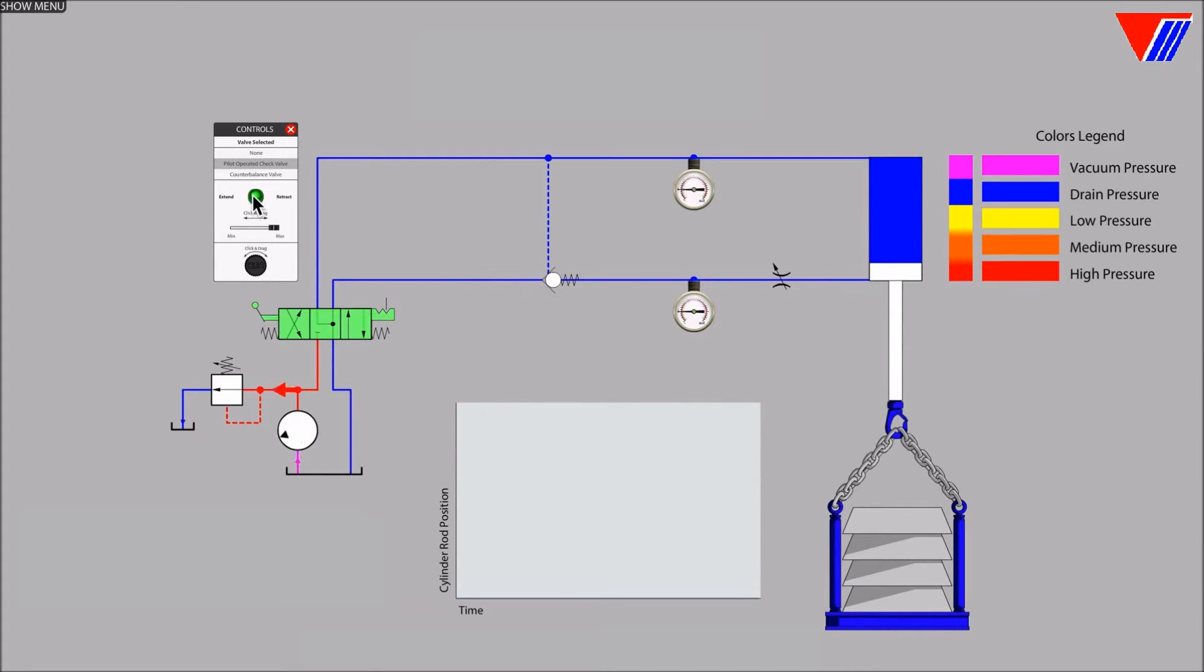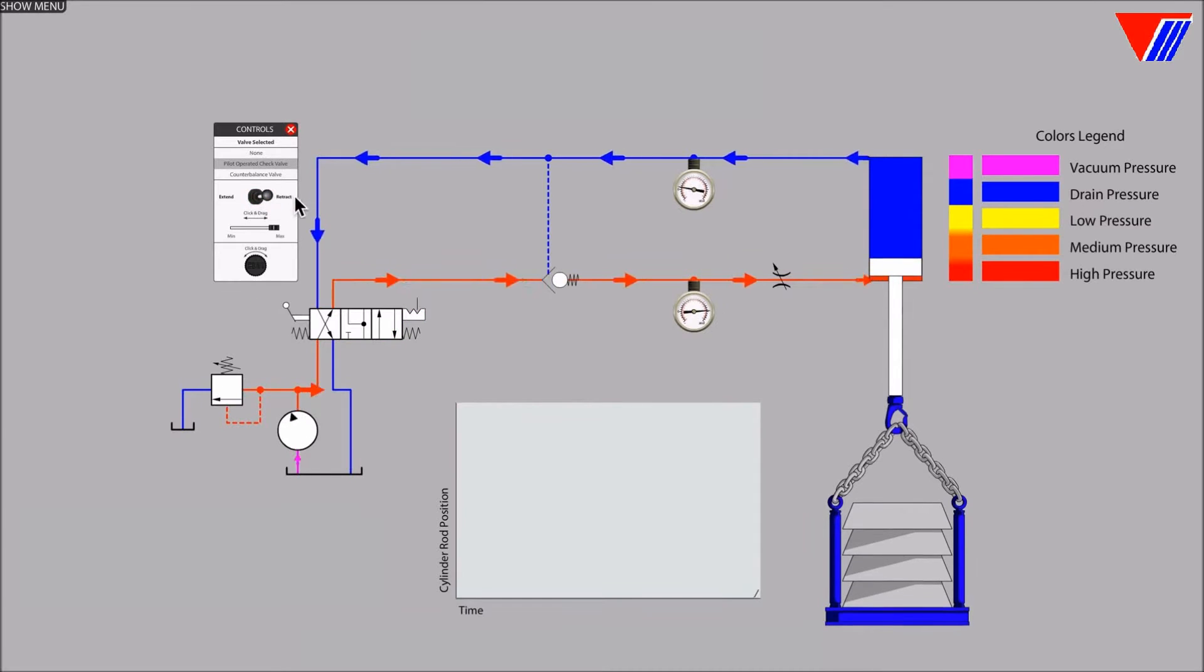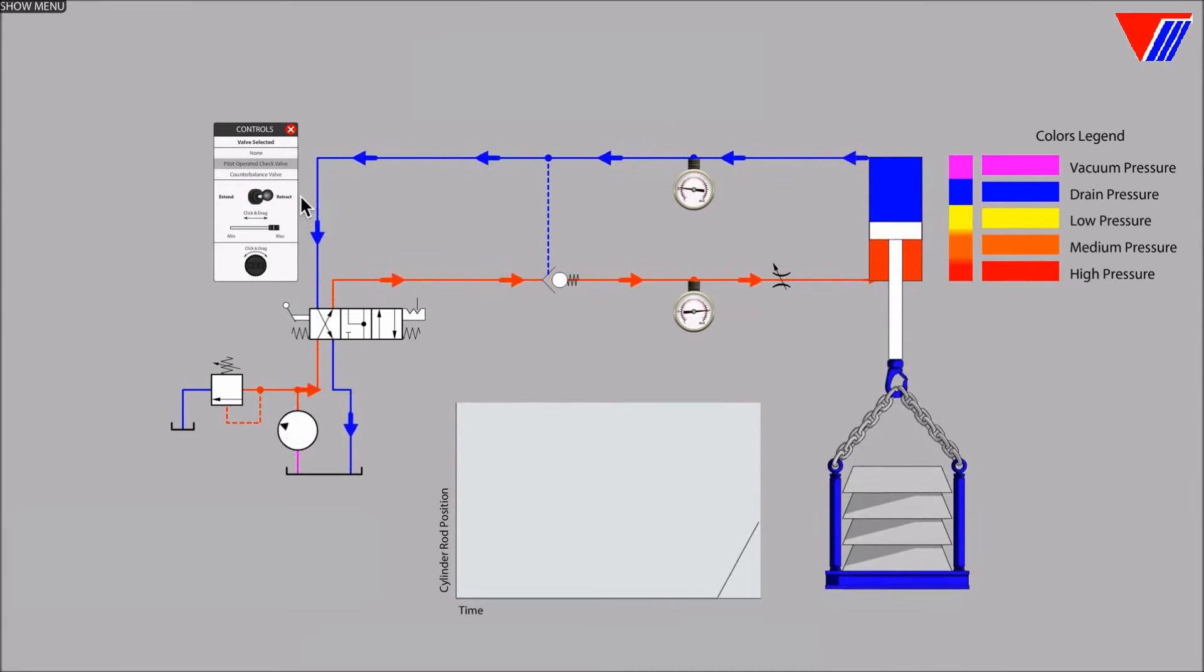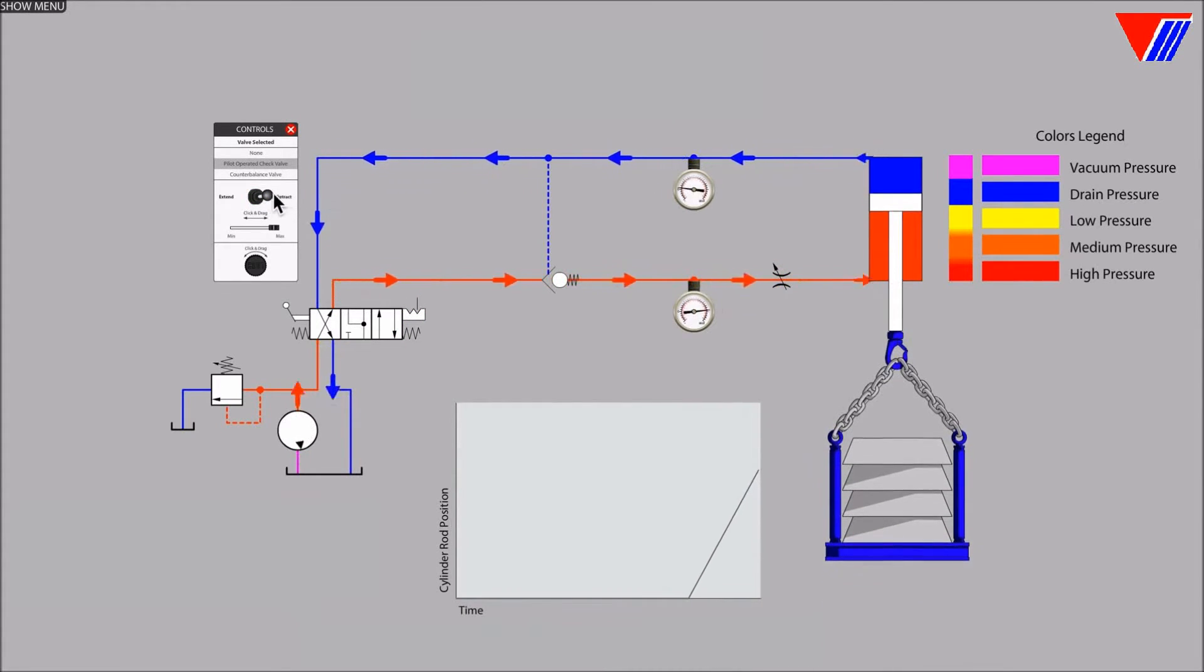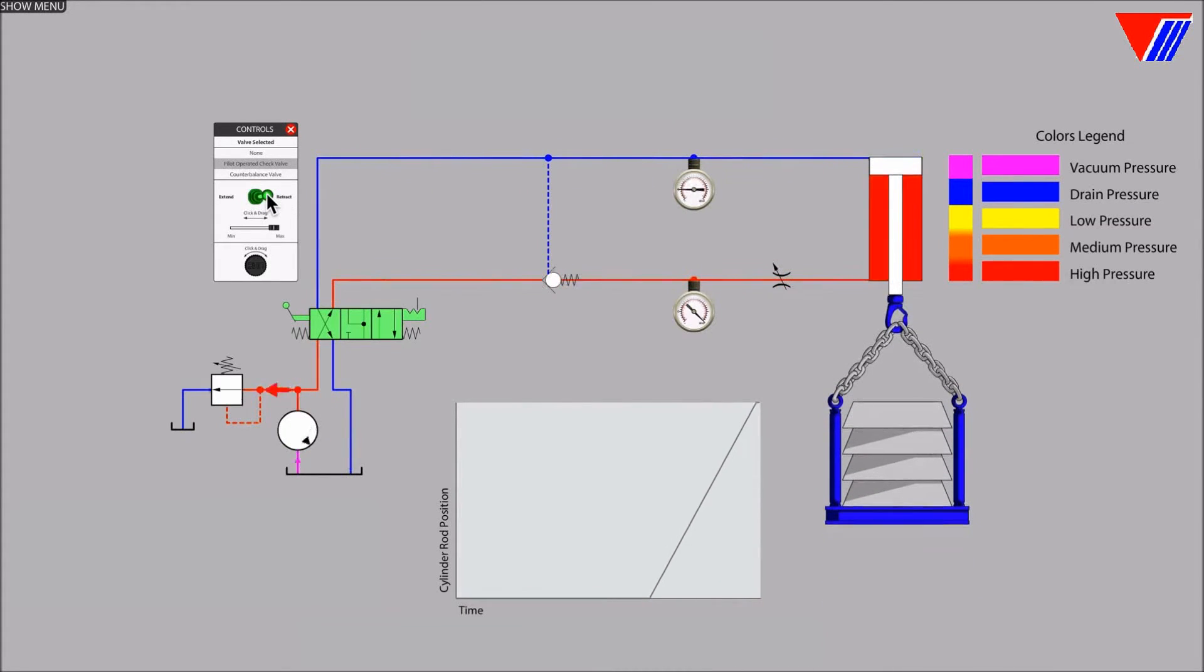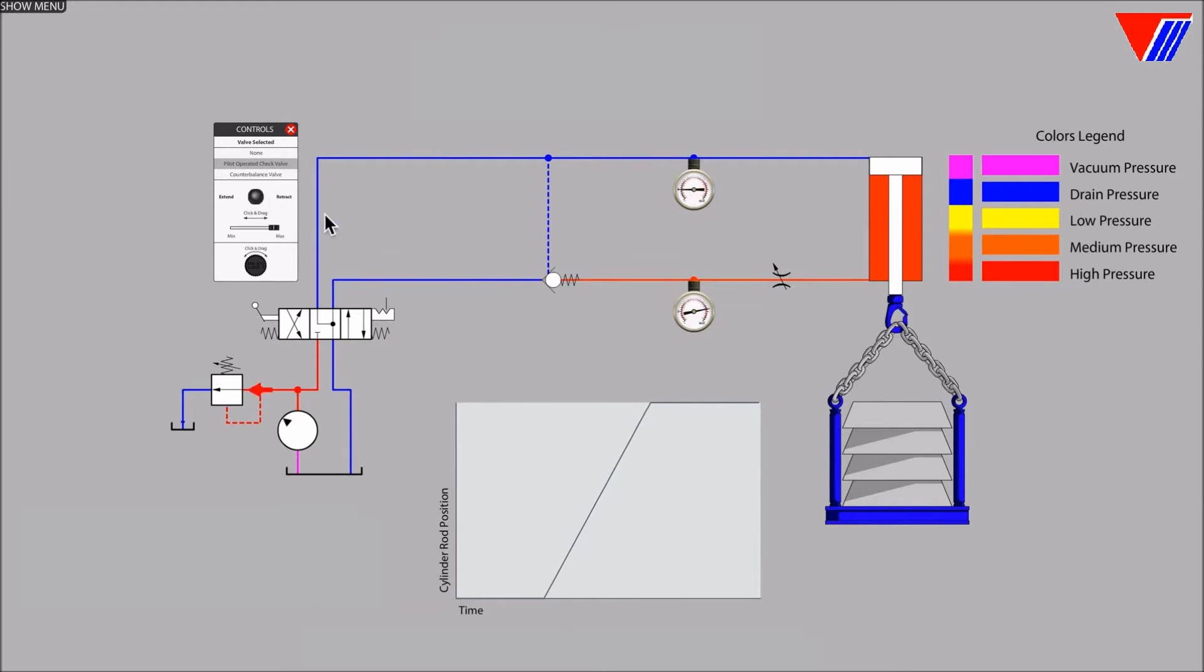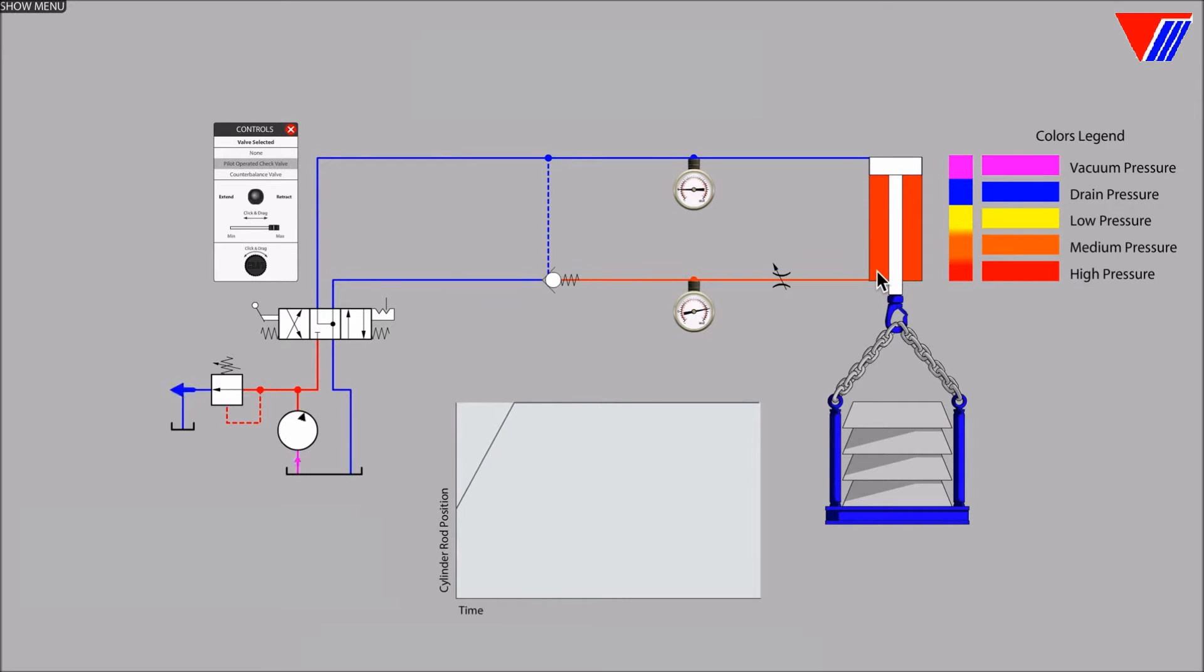Let's operate the directional valve to retract the cylinder raising the load. Releasing the handle on the directional valve shows us that the pilot operated check valve is indeed holding the load. Notice the graph that shows the cylinder position over time.